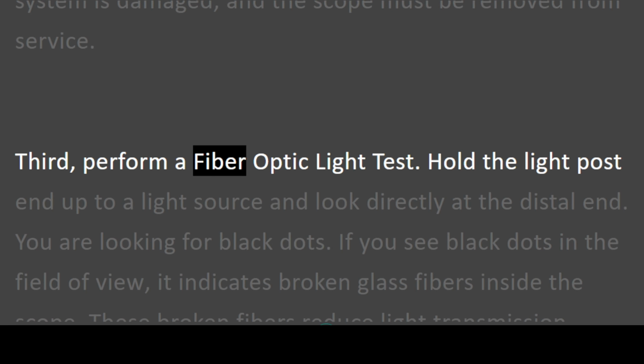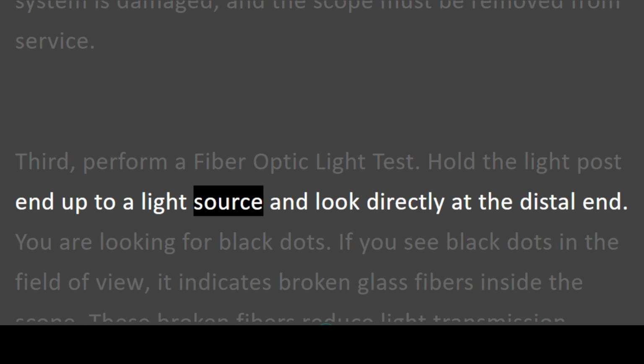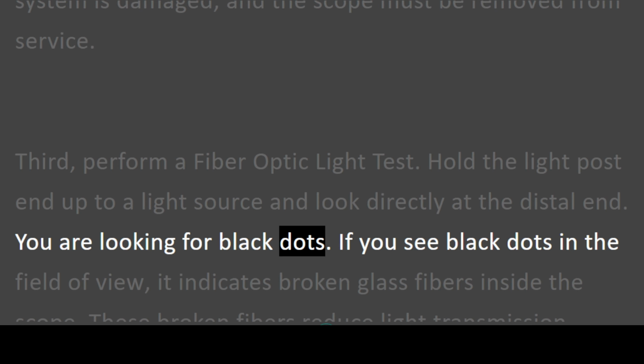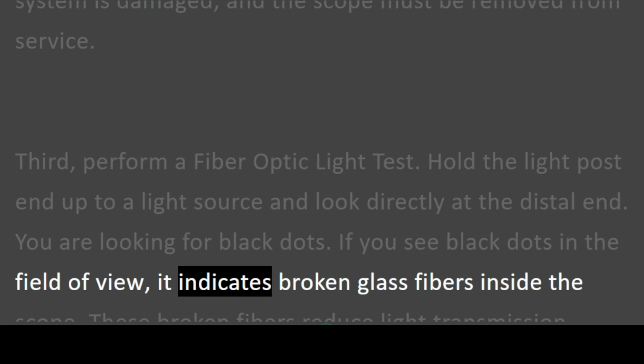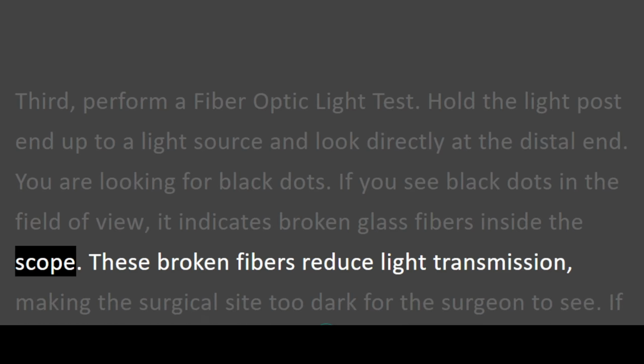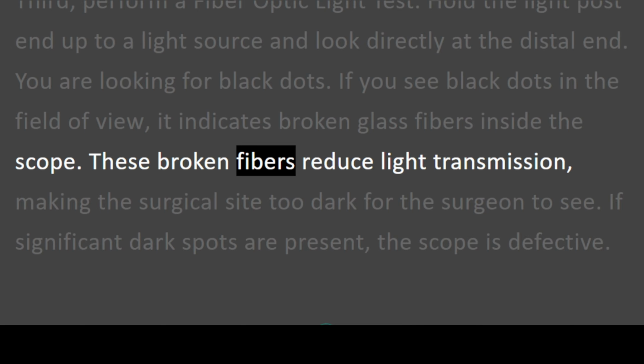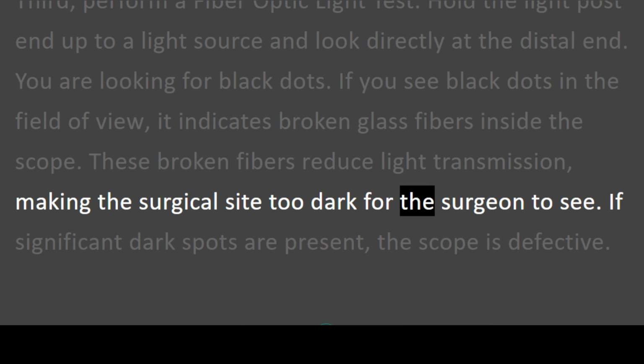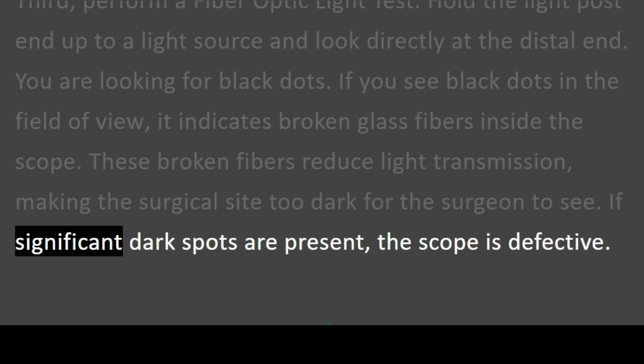Third, perform a fiber optic light test. Hold the light post end up to a light source and look directly at the distal end. You are looking for black dots. If you see black dots in the field of view, it indicates broken glass fibers inside the scope. These broken fibers reduce light transmission, making the surgical site too dark for the surgeon to see. If significant dark spots are present, the scope is defective.